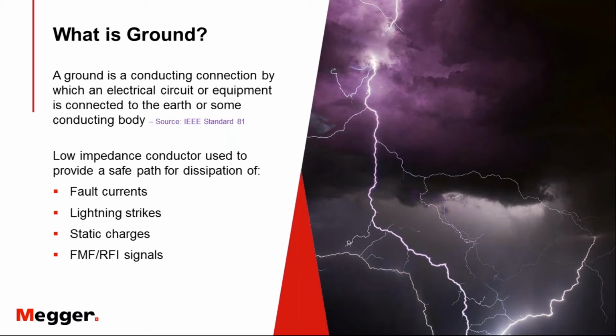Similarly, fault currents behave much like lightning. The utility has a problem, something occurs causing a fault current, and that current tries to find its way to ground. You want it to go through a grounding electrode, not through your equipment, and most importantly, not through a human being. If a voltage gradient develops across your equipment and a human contacts it, that person could become the best path to ground. You want to eliminate that possibility with a good parallel grounding system.